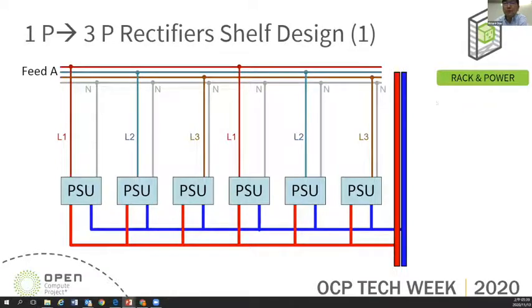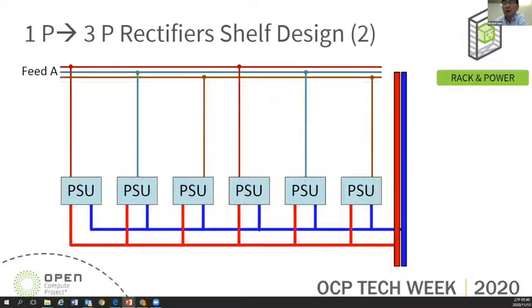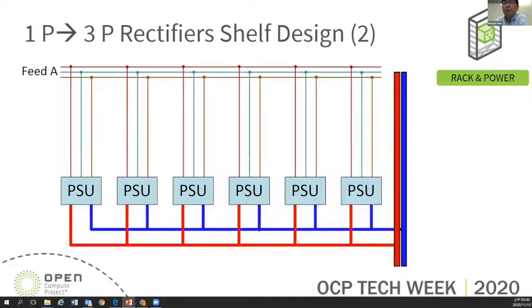So this is an example for the single phase. In the single phase design, normally we do it this way. We connect number 1 and number 4 power supply with phase 1 and neutral. Number 2 and number 5 power supply connect with phase 2 and neutral. Number 3 and number 6 connect with phase 3 and neutral. So when we change the power supply to 3-phase, we remove the neutral wire first and connect with the 3-phase input. Since it is 3-phase, the current will be a little bit smaller, so we can use a smaller wire for that and connect the output together.